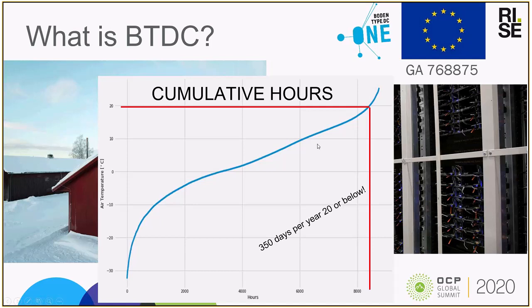Now, the cooling units that we use have evaporative functions, so if we do get a very hot summer day, then we can wet the pads and evaporate water into the airstream to humidify the airstream, but also to drop its temperature. So in these challenging environmental conditions of hot weather, we can use the evaporative function. And in the very cold conditions where we do not bring very much fresh air in, we recirculate a lot of the hot air in the data center, then we would need to humidify the air.